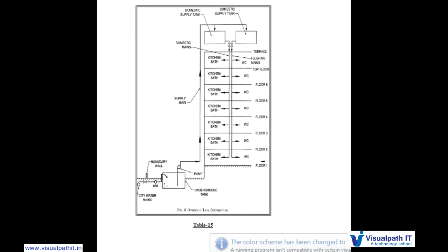And so as per the definition, we need to supply water from desired sources. The source may be a borewell or municipal water or water tankers. Here in this drawing we can see city water mains. We are getting water from city water mains, and here we are having a valve. It may be a ball valve or butterfly valve, depending on the size we will use. Generally, till 50 mm dia we will use ball valves. If it is more than 50 mm dia we will use butterfly valves.